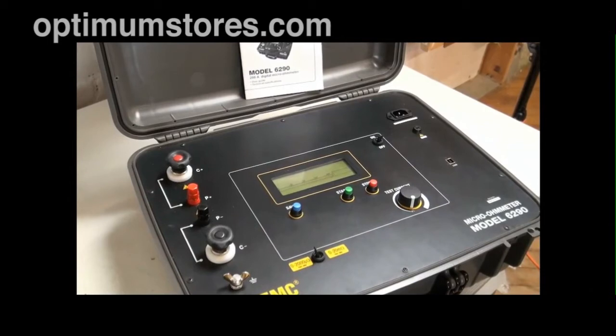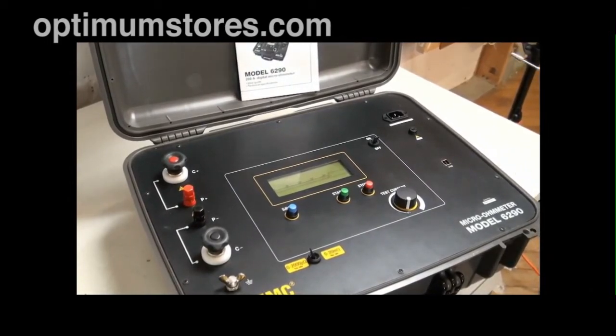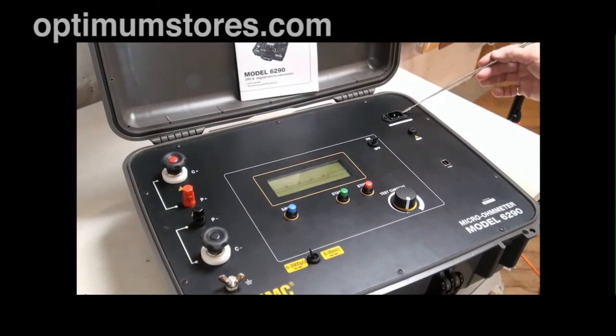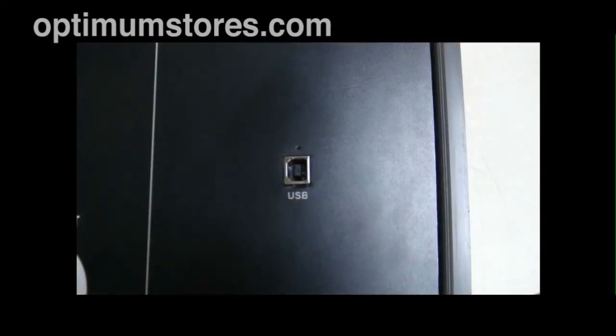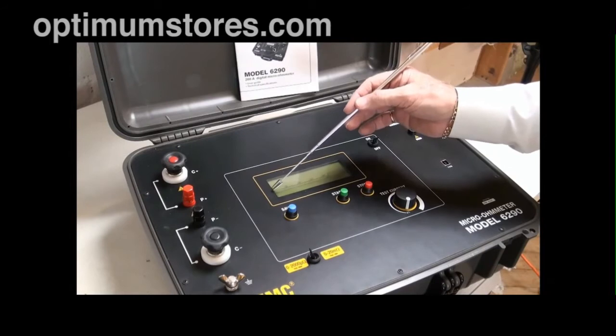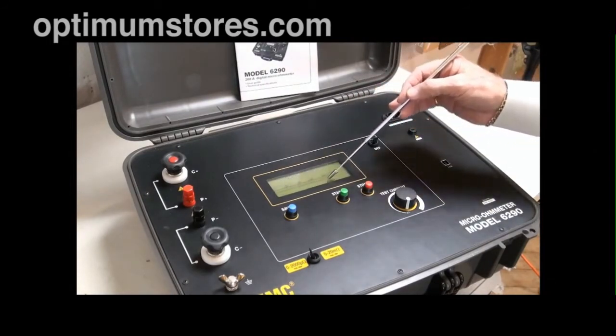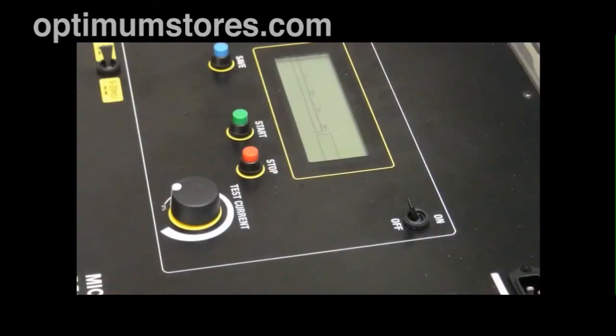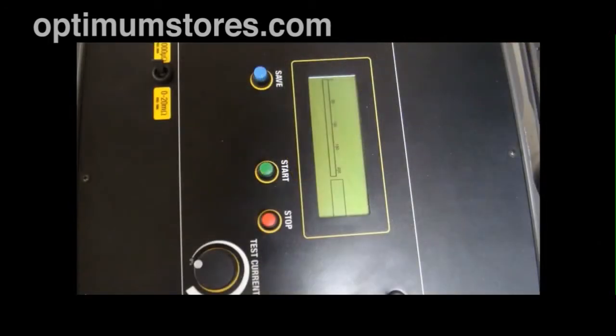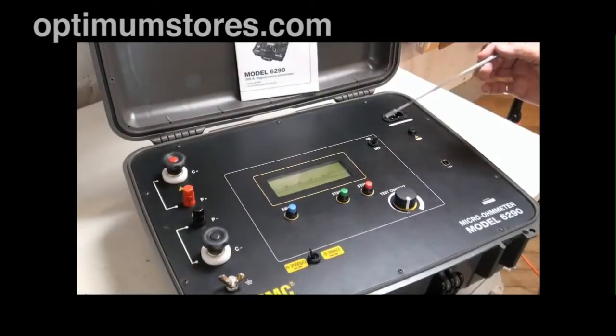Now, taking a closer look at the instrument, we see first of all a very simple layout that is ideal for ergonomics and customer end use. Starting with the input power, because we have such large wattage, watt seconds, it requires external power. It has fuse protection. Here's your USB port for downloading your tabular listing of your test experiments. Here's your vernier control, which allows us to control the output, and we have a gas gauge, if you will, that will show the relative position of the output current. We will have a digital display, we'll show you that in a minute, that will read the date, time stamp of the test, the actual resistance value and the current being applied.